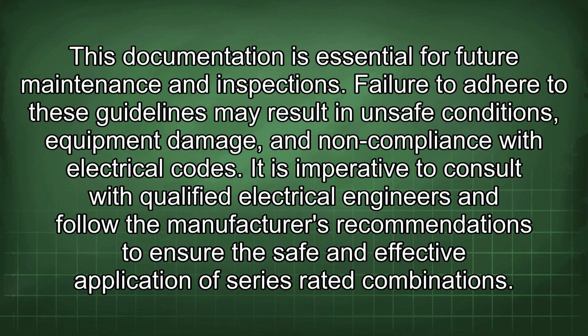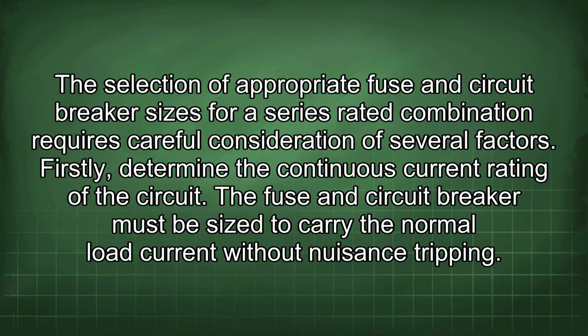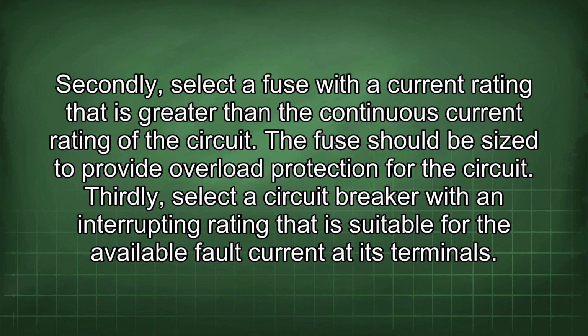application of series-rated combinations. The selection of appropriate fuse and circuit breaker sizes for a series-rated combination requires careful consideration of several factors. Firstly, determine the continuous current rating of the circuit. The fuse and circuit breaker must be sized to carry the normal load current without nuisance tripping. Secondly, select a fuse with a current rating that is greater than the continuous current rating of the circuit.